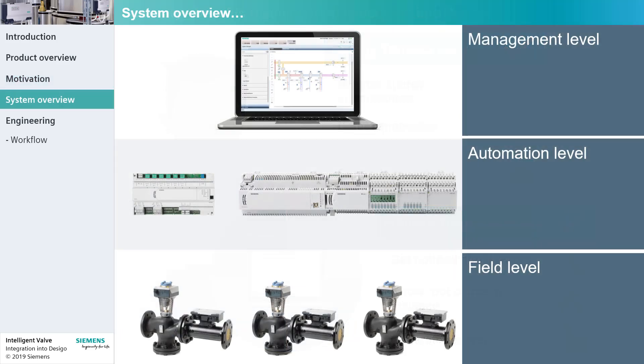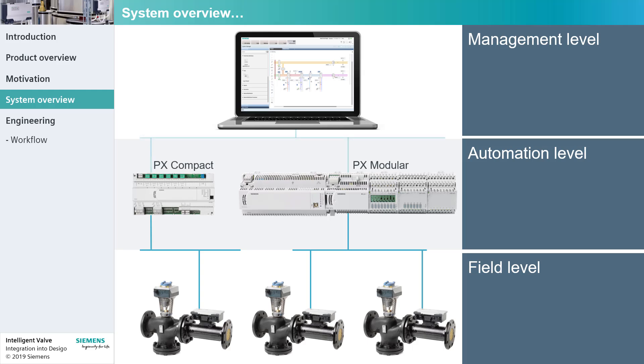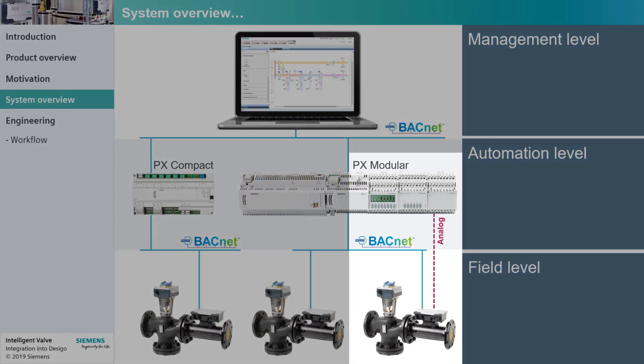Let's take a look at the integration of the intelligent valves. The intelligent valves are connected to and controlled by a higher-level automation station — in this case, either a PX Compact or a PX Modular. To display the data in Desigo CC, integrate the PX Primary Automation Station into Desigo CC. All the communication is based on BACnet IP. Alternatively, intelligent valves can be controlled via an analog signal.